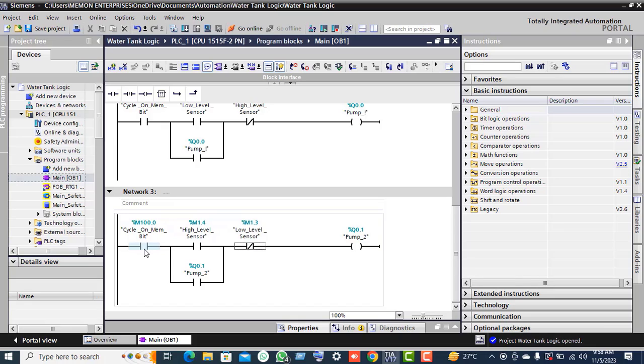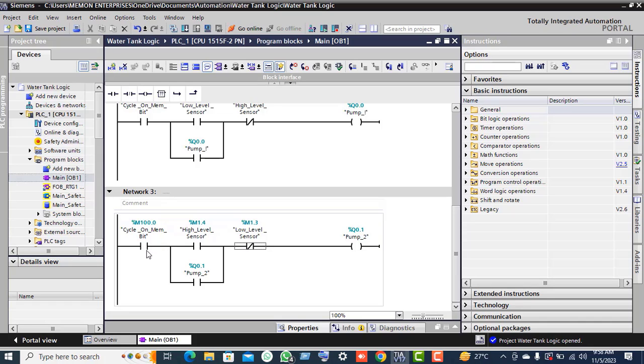When the operator presses the start push button, the NO contact becomes an NC contact. If the water level is high, the high level sensor NO contact becomes NC, allowing current to pass through. With the low level sensor already on, pump two also comes on and remains latched with the Q0.1 pump two contact.